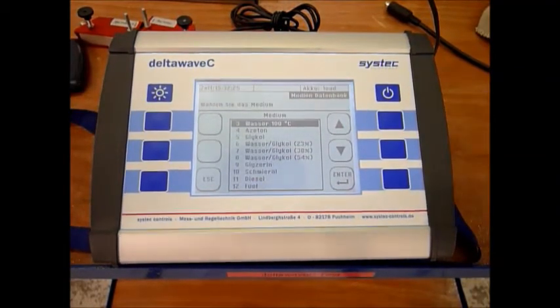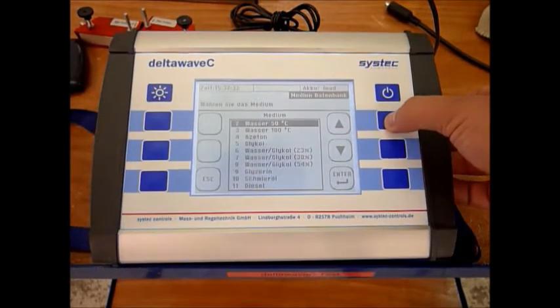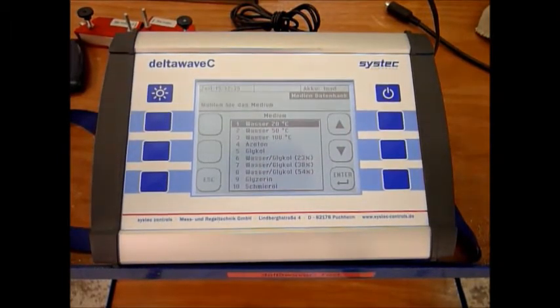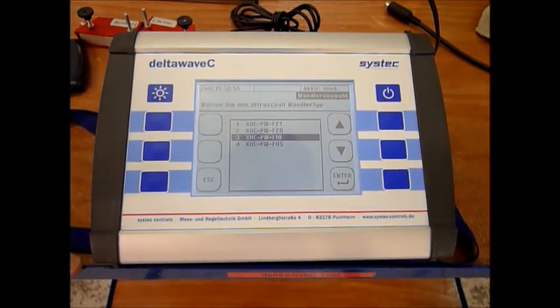Last but not least, the flow meter is asking for the fluid. Delta Wave has an integrated database with various fluids such as water, water glycol, various oils, benzene, and so on. It's not necessarily important that your exact fluid is stored in Delta Wave because Delta Wave is actually measuring the sonic velocity of the fluid. If you make a mistake, it will do an automatic compensation.